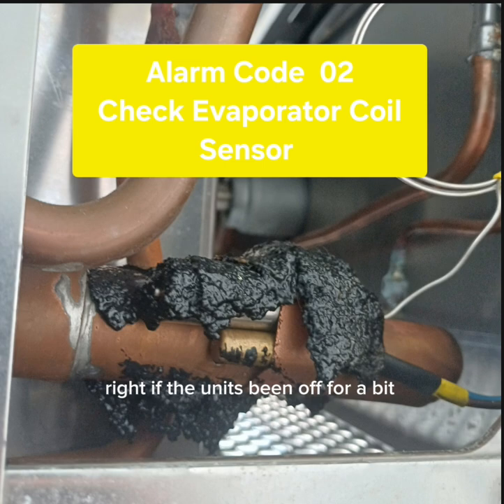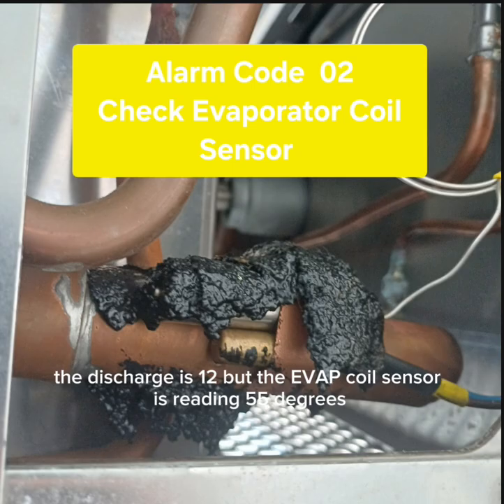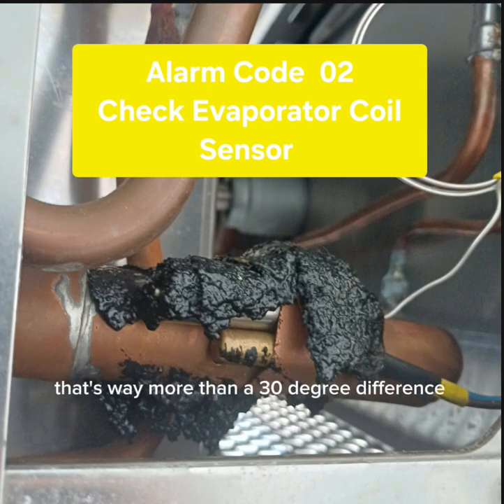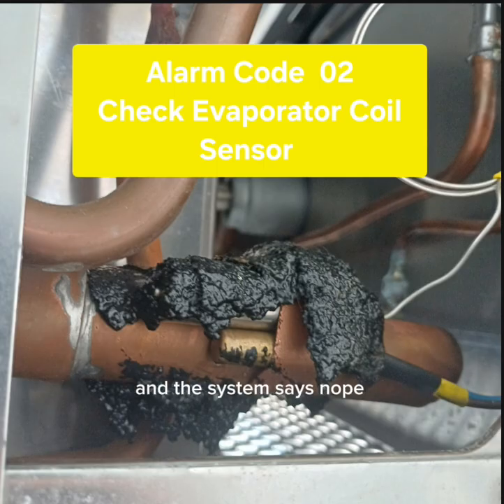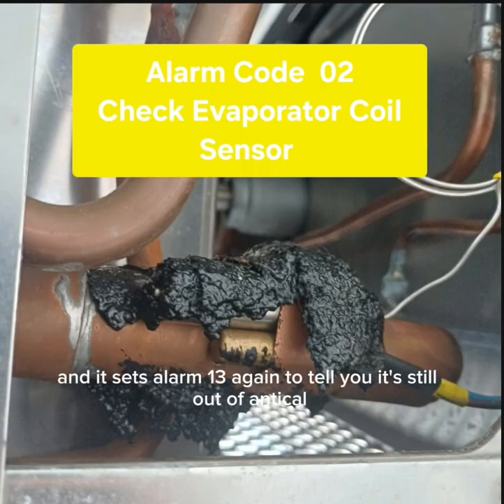Right. If the unit's been off for a bit, they should be relatively close. So if the return is 10 degrees, the discharge is 12, but the evap coil sensor is reading 55 degrees. That's way more than a 30-degree difference. And the system says, nope. It assumes the sensor is still inaccurate. It will not clear the alarm. Alarm 02 stays, and it sets alarm 13 again to tell you it's still out of calibration.